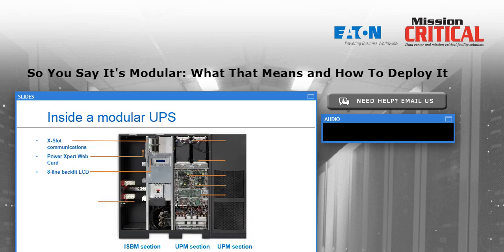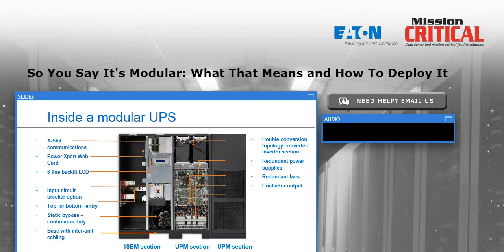So what do we see inside a typical modular UPS? This happens to be one of ours, but you'd be looking for these features in any modular scalable UPS. And by the way, most vendors in this industry now offer UPSs that are in fact scalable. So the kinds of things you look for, starting at the left-hand side here, where the bus bars are mounted for connecting the battery, the input 3 phases, the output 3 phases, and the bypass utility line for the UPS, all connected over there in that far left-hand end. Most large clients want the ability to have top and/or bottom cabling depending on their application. The bus bars are positioned so the installer doesn't have to pull heavy cabling into that area and then bend that cable to match the bus bars. It simply comes straight up from the floor or straight down from the ceiling and lands on the bus for a relatively easy and uncrowded installation.